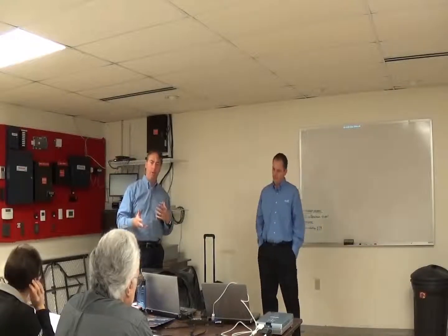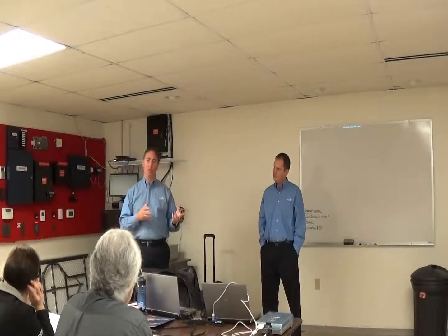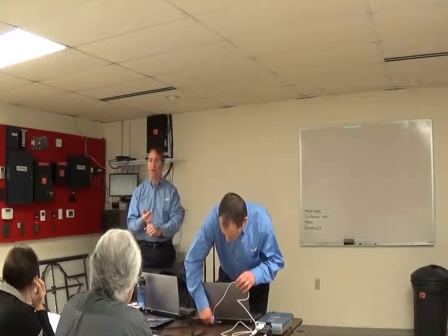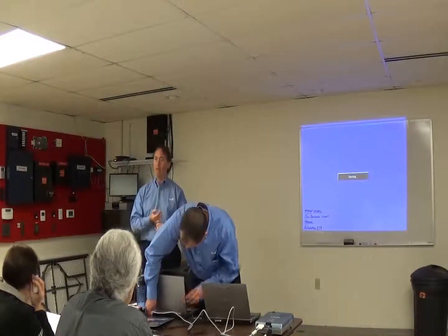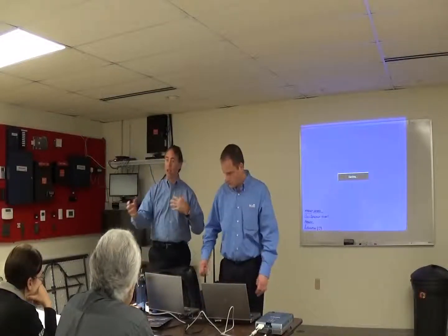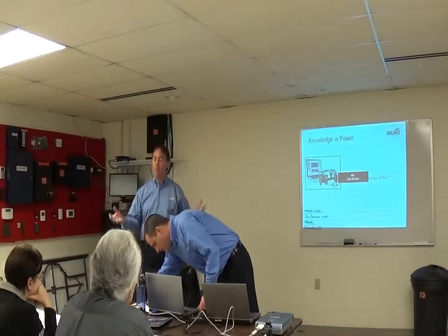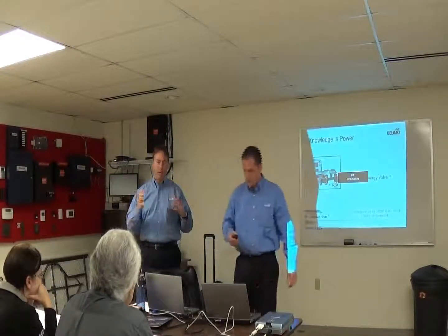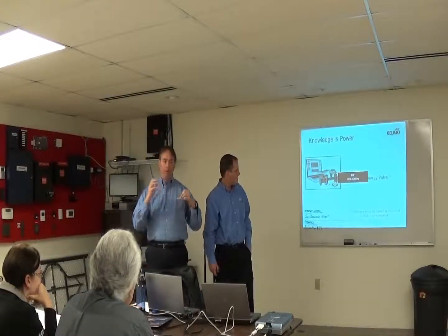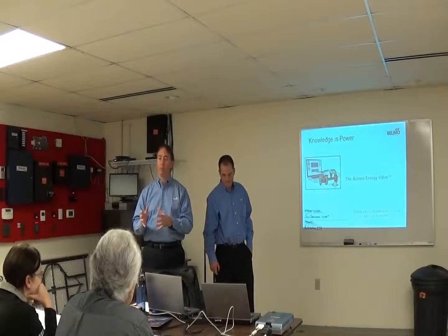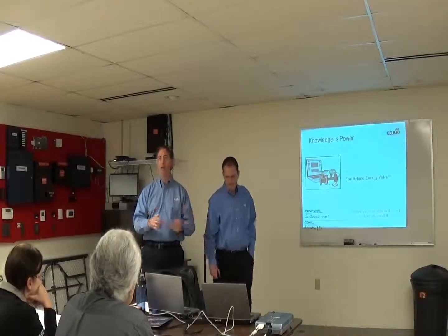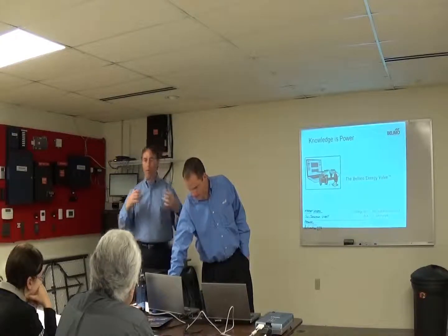Well, the other thing is, in looking at some of the smaller valves, we've seen, in looking at 1/2 and 3/4 inch valves, if you just take the total installed cost into consideration, rather than just the unit price of the valve, the fact that you're gonna eliminate the need for a circuit setter or some type of balancing valve, you may not need to have the balancer go to each coil, but balance the system as a whole. Some of the savings that you can achieve, on the 1/2 and 3/4 inch size, you end up seeing that the pressure independent ends up costing less total installed than pressure dependent.